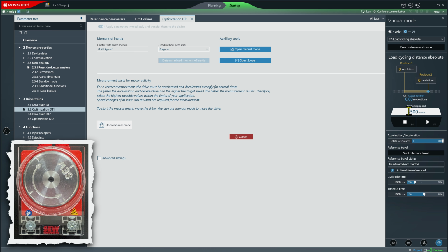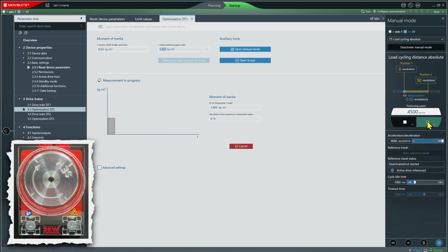I need to set my speed. I'm going to set it to the motor's maximum speed, 4,500 RPM. And I'm going to set position 1 to 0, which it already is, and position 2 to 50 revolutions. What will happen is, as my motor cycles back and forth between 0 and 50 revolutions, it will determine the inertia. So here we go, let's do that. Click play. You can see the motor's going back and forth now. And notice a graph appears over here with bars. Each one of these is an inertia measurement.